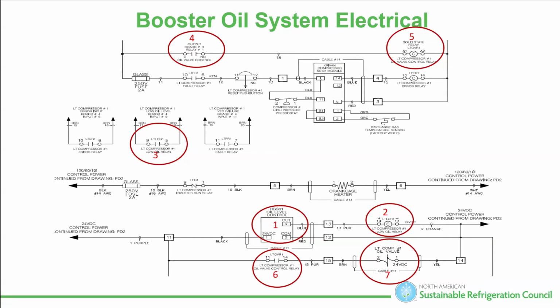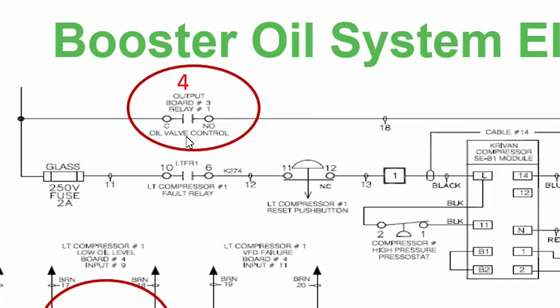It's going back to source, AC or DC. AC and DC, greatest rock and roll band ever. Sorry. But I'm going to go, okay, he's not energized. Why? Where did I open the circuit? Well, being lazy, I'm going to go up here. The relay point, the board is right here in front of me. The electrical panel, it's right there. So I'm going to pop my meter right here. If I have, this is 208, I'm on T2. If I have 208 here, which way do I go? I know the controller said go. I know the controller closed the relay. I'm going this way.